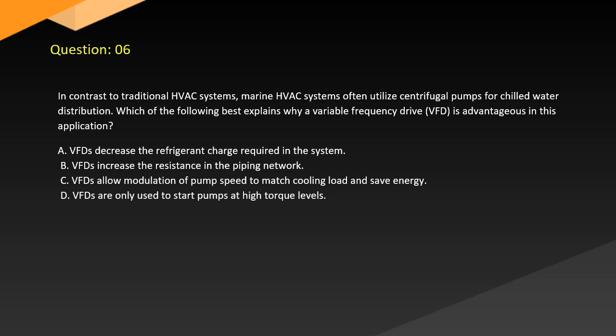Question 6. In contrast to traditional HVAC systems, marine HVAC systems often utilize centrifugal pumps for chilled water distribution. Which of the following best explains why a variable frequency drive, VFD, is advantageous in this application? A. VFDs decrease the refrigerant charge required in the system. B. VFDs increase the resistance in the piping network. C. VFDs allow modulation of pump speed to match cooling load and save energy. D. VFDs are only used to start pumps at high torque levels.